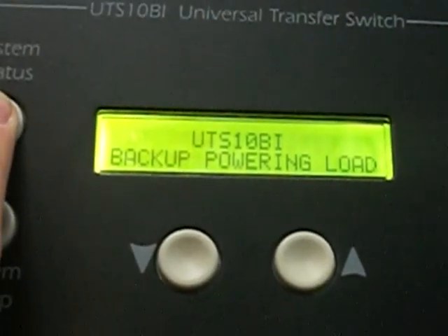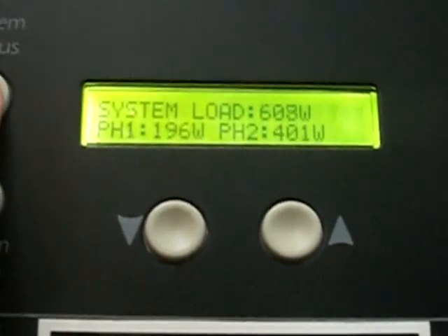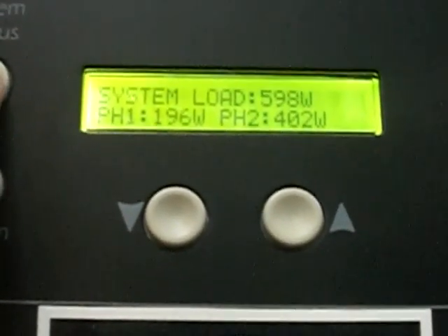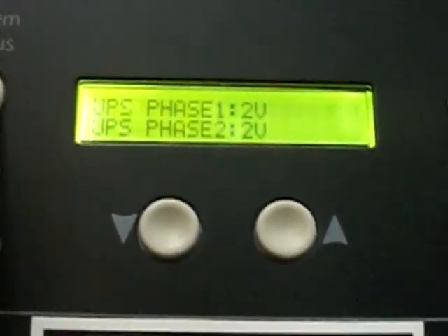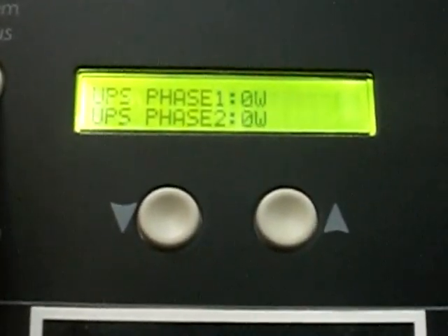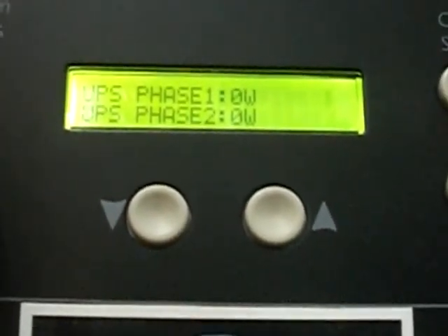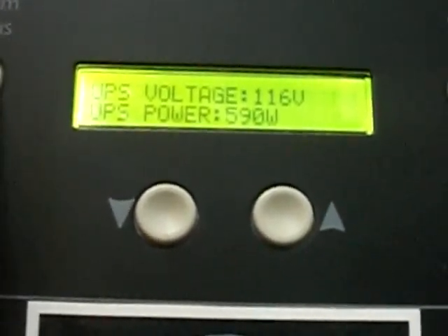Then you've got this button here — system status — which tells you the whole thing: what's on each phase, what each phase wattage is. Total watts are 608. Each phase in the UPS shows zero watts, UPS voltage, and UPS power.